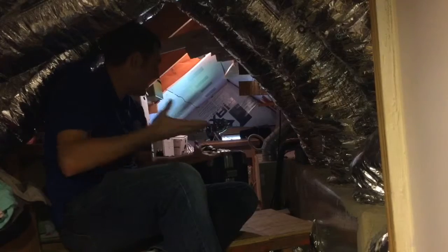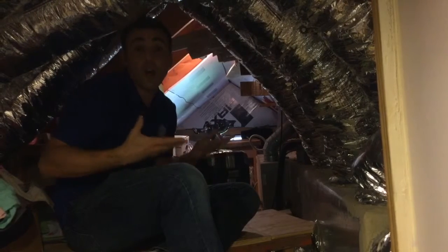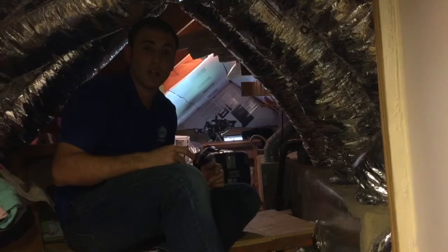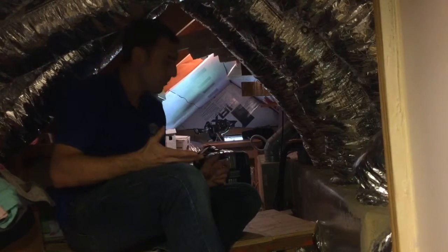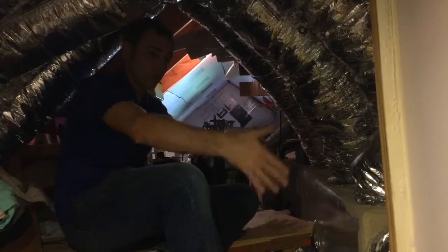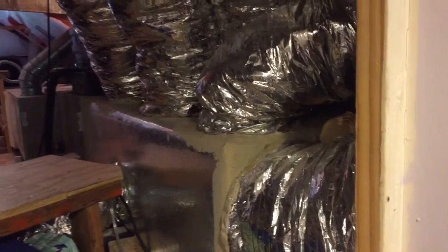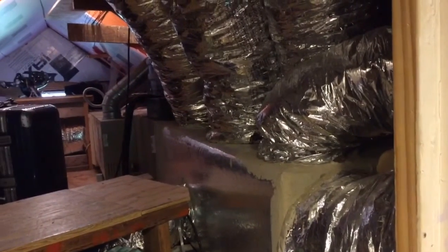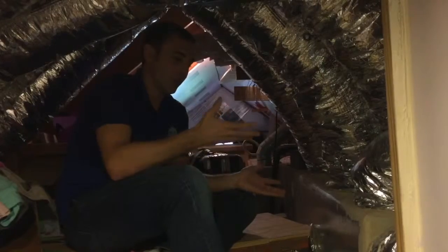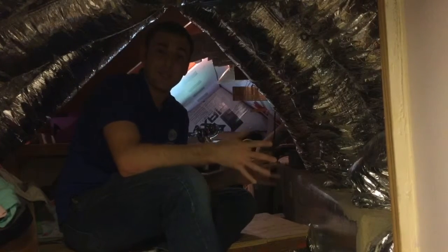But you can see in this particular environment, you can never build ideally. You just want to sort of strive and know what's best practices and what a good design can do. So in this situation, they had to have all of their ducts coming off the top. They only had this much room to put the ducts in, so it ended up rather cramped. So you can see that this is a pretty typical design, and it's also very common practice to sort of leave the mechanicals till the last minute.